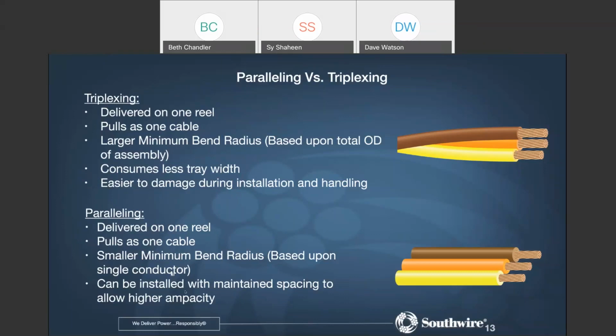Now, up at the top, we have triplexing. Triplexing is also going to be delivered on one reel. It's going to pull as one cable, but now these conductors are all twisted together. And there are some possible electrical reasons, I'm not getting into that in today's presentation, of why you would want to plex those conductors together. But what you will end up with is now the bend radius is going to be based upon the total OD of the assembly, because when you bend this, you're bending three large conductors in an assembly. So you're going to have definitely a larger bend radius that you'll have to take into account during the installation process.